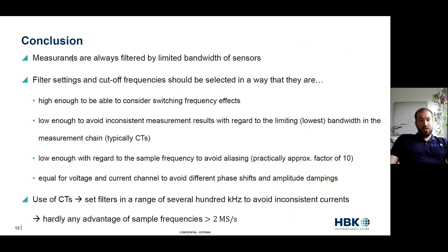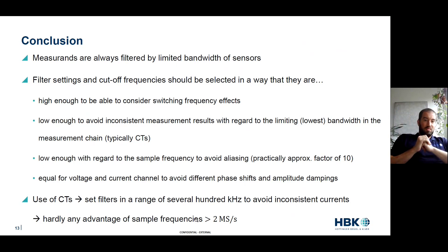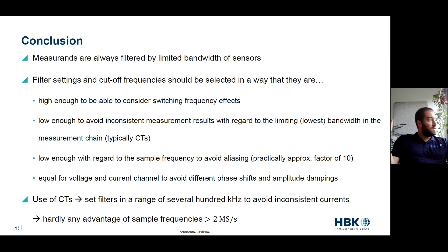In conclusion: measurements are always filtered by the limitations of sensor bandwidth. Filter cutoff frequency should be high enough to capture switching effects, but low enough to avoid inconsistent measurements, aliasing, and CT bandwidth issues. Keep the filter low enough relative to the sample frequency to avoid aliasing — by about a factor of 10. Use equal filter settings for voltage and current to avoid phase shifts. When using current sensors, set filters lower than the current sensor bandwidth. There is really no advantage to going above one mega sample. Most customers run at 500 kilohertz sample rate, filter to 100 or 50 kilohertz, and are perfectly happy with 8 kilohertz switching frequencies.